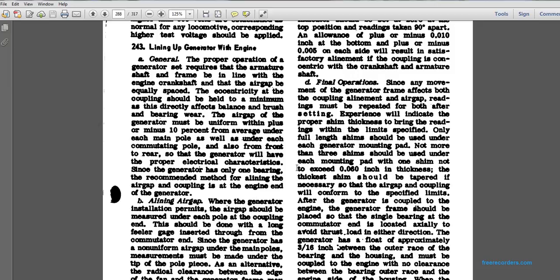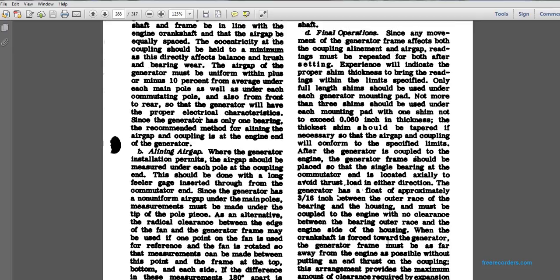The thickest shim should be tapered, if necessary, so that the air gap coupling would conform to the specific limits. After a generator is coupled to the engine, the generator frame should be placed in a single bearing at the commutator end, located axially to avoid thrust load in either direction, for the generator to have a float of approximately 3/16 of an inch between the outer race of the bearing and the housing, and must be coupled to the engine with no clearance between the bearing outer race and the engine side of the housing.